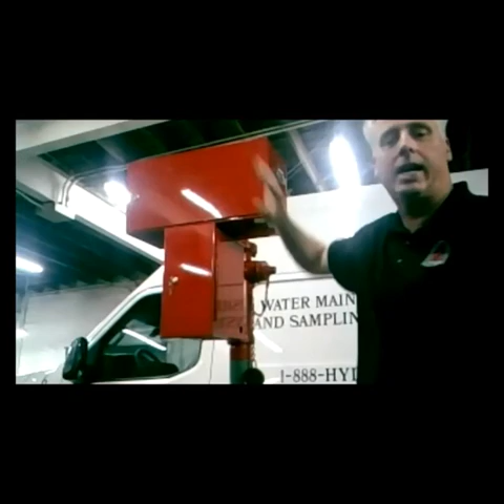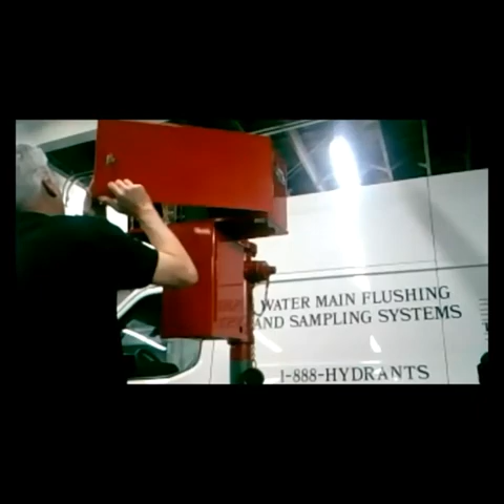There's a solar panel on top like we saw in the picture, and the water flushes below the box here. This has a 2.5-inch NST connection, and I connect it right to the fire hydrant or the blow off. Up here at the top portion, we have all of our electronics and sensors, and on the bottom is your flushing section. It actually flushes the hydrant with the 2-inch automatic flushing valve.